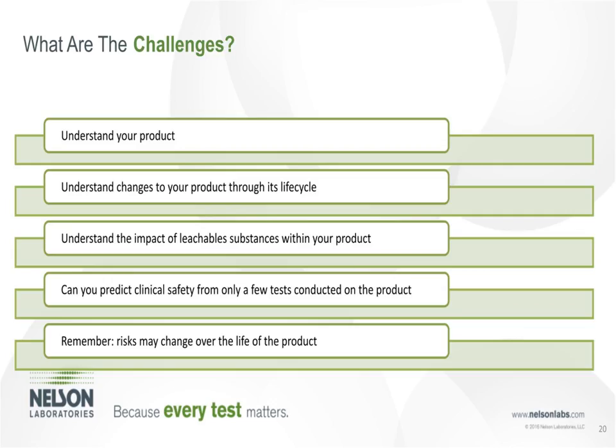We had one recently, it's been a couple years ago, that changed locations. And when they changed locations, same device, same employees, same even machines, but when they changed locations, they started failing cytotoxicity. When they performed a chemical analysis, they found out that it was a chemical that's been used in surfboard manufacturing, and their neighbor just happened to be a surfboard manufacturer. So there are things that could evaluate through the life cycle that could have a change or an impact to safety.